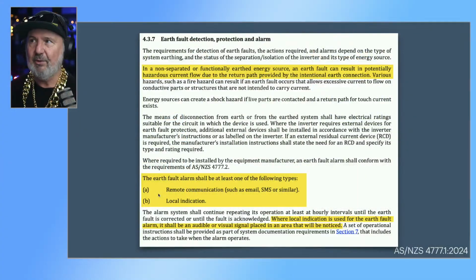So coming back to earth fault detection, where local indication is used for earth fault alarm, it shall be an audible or visual signal placed in an area that will be noticed. So that's the point I'm making with that story, that it was in a location that no one would really notice, because it's too hard to read the word next to that little red light. So, yeah.